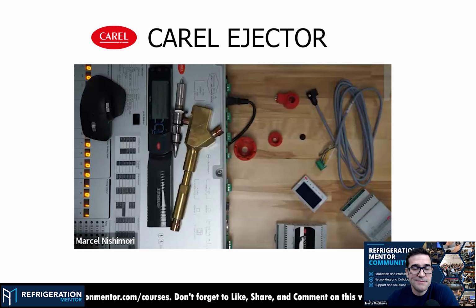I've been to some sites and I can testify to what you are saying. Most of the time we might find a couple of bits of dirt inside the system. So a filter before the ejector is highly recommended, or even mandatory, for the better performance of the system. Yeah, and that's in your instruction manuals too. It recommends that, and we're not supposed to have dirt in the system, but it consistently happens. So make sure you protect the most important components.